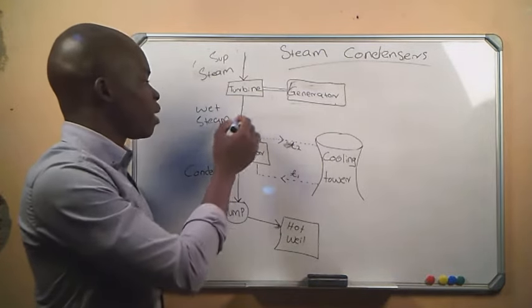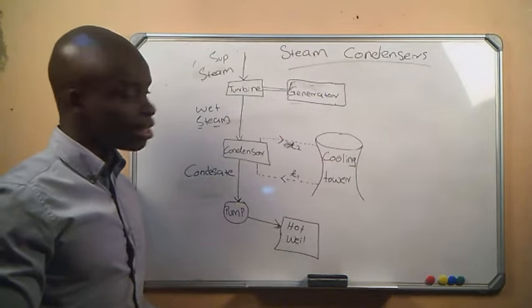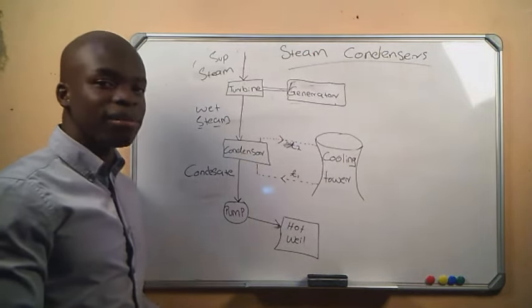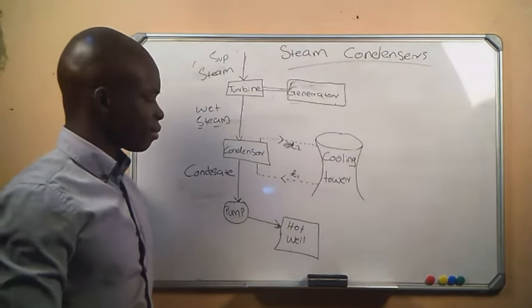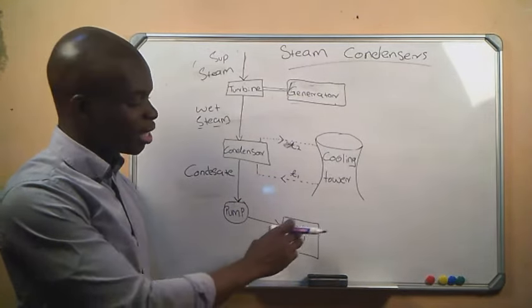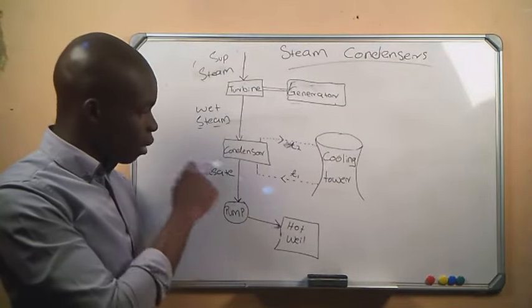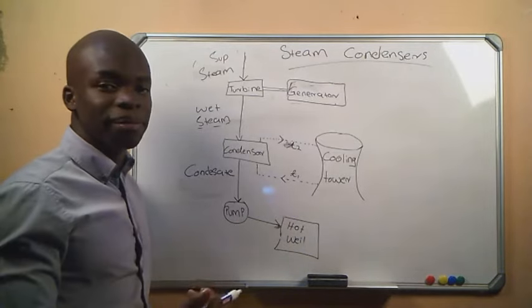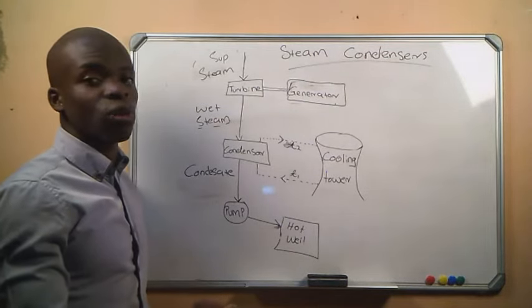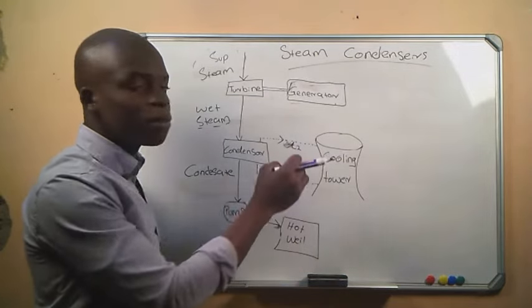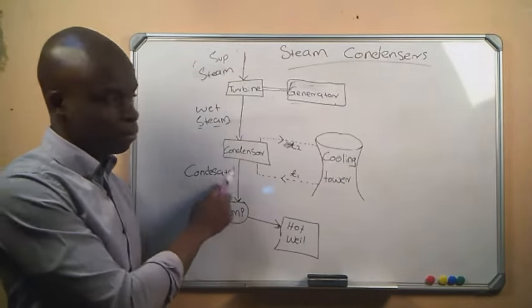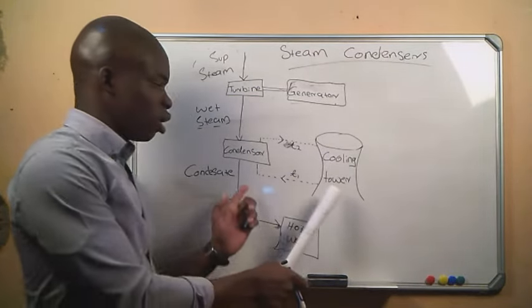When the steam comes out from the turbine, it comes out as wet steam — no longer superheated. We then have a device called a condenser, which is used to convert the steam into condensate, which is water. That water is pumped by a pump to a hot well for storage. In the condenser, the steam is converted into condensate with the help of a cooling tower, which provides cool water to absorb the heat energy from the steam.